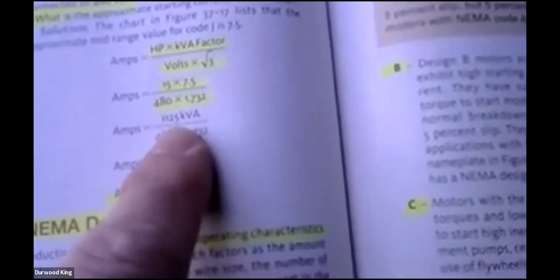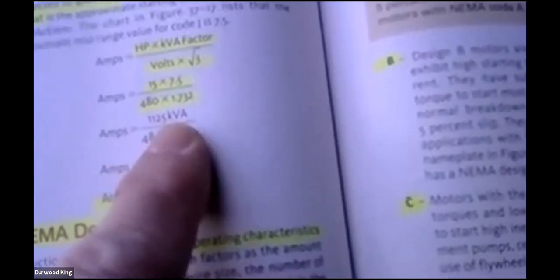That's the startup amps for a 15 horsepower motor, three-phase at 480. So that's a lot of amps on startup. That's called the locked rotor amps, from a dead still. I'm sorry, 135 amps. My bad. The answer is 135. I'm trying to look at the camera plus this. So the top two numbers, when you multiply 15 times 7.5, it ends up being 112.5 kVA, which is 112,500 volt amperes. Divided by 831 gives you 135 amps. So that's the startup amps. That's your inrush for a 15 horse motor, three-phase at 480.